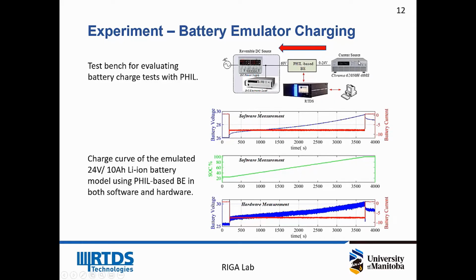And also because it is a current source, that means providing a constant current to the battery emulator. So you can see here there is an 8 amp current being provided to the battery. That's why the battery voltage is going up in this way until we stop the testing. And also in the software internally, you can see that it is going up as well. And you can see that the SOC is increasing until it reaches 100%.